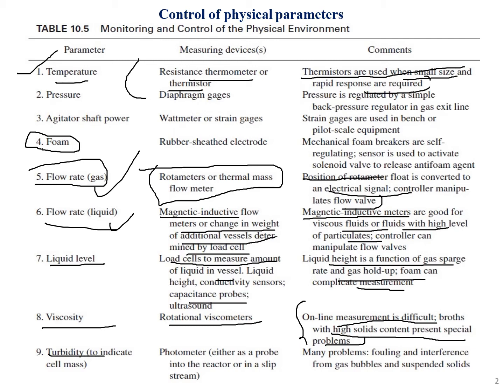The ninth parameter is turbidity, which is very important when studying bioreactors. Turbidity is measured with the help of a photometer. There are many problems with using photometers, which include fouling and interference from gas bubbles and suspended solids.